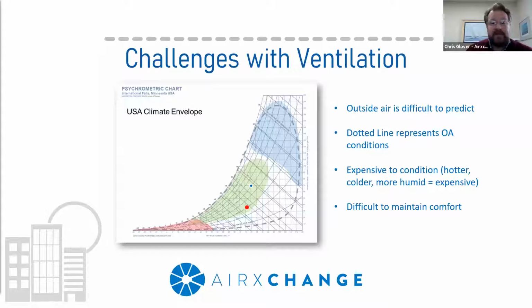So outside temperature is very difficult to predict. If you look at the psychrometric chart to the left, you can see that you have large swings in outside air temperature and humidity. What that dotted line represents is that at any given point on any given day, your operational point could be within that dotted line.